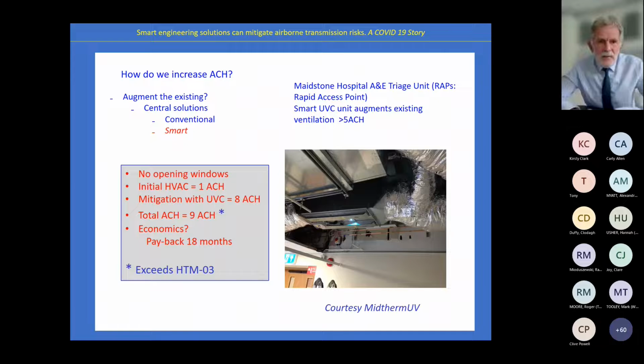You can't open the windows, so here's an example of putting a bit of additional kit in the ceiling of a healthcare space. It's actually the access room ahead of the A&E department of a hospital. A small piece of kit raised the inherent air changes per hour from 1 to 9, using ultraviolet technology, which I'll explain in a moment.